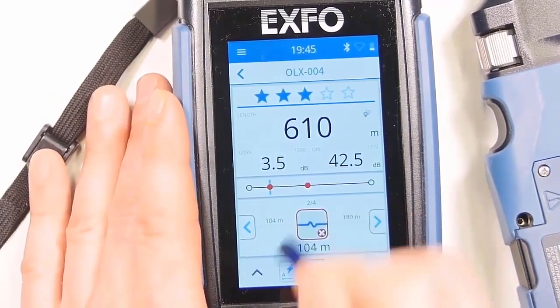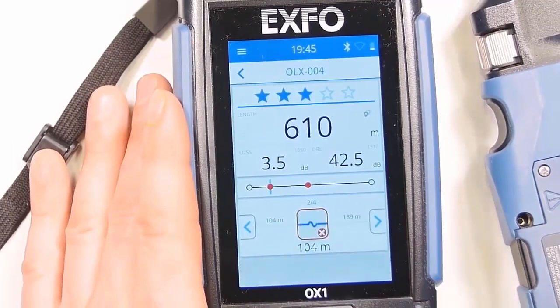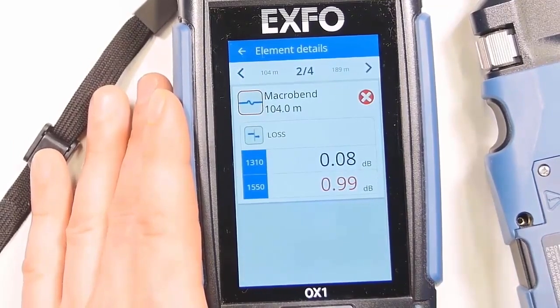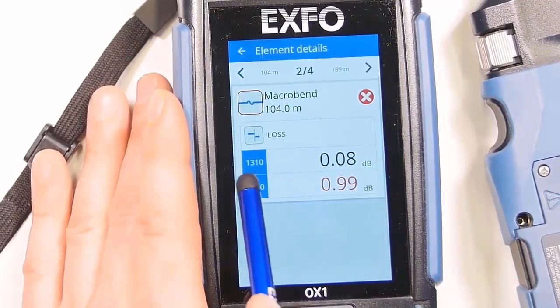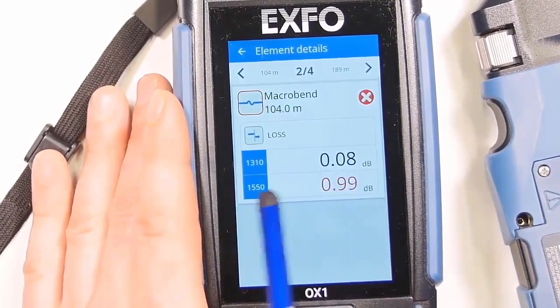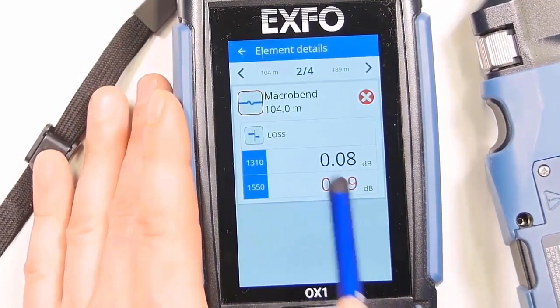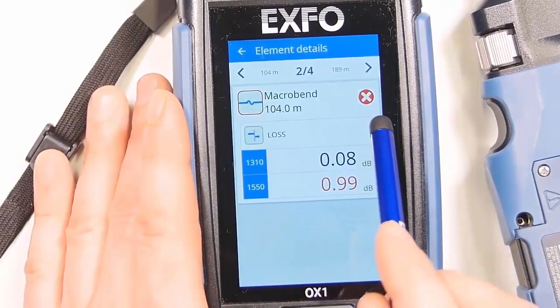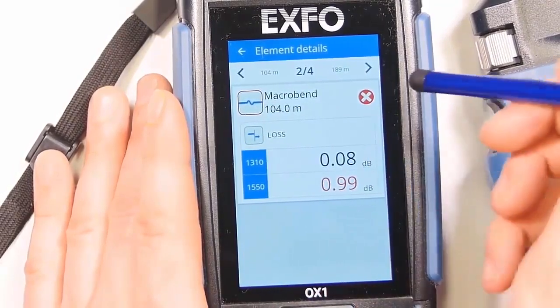At 104 meters we have a macro bend. Now this is the fault explorer that we're using as it transitions to the next test.